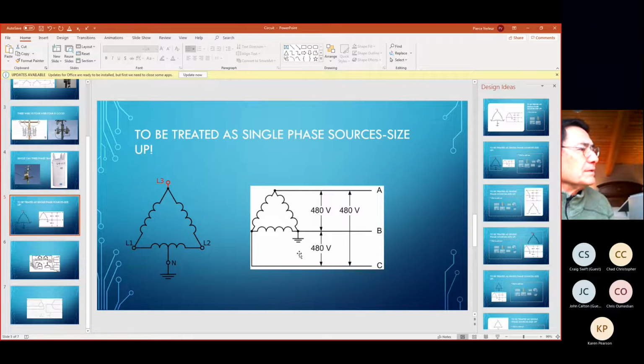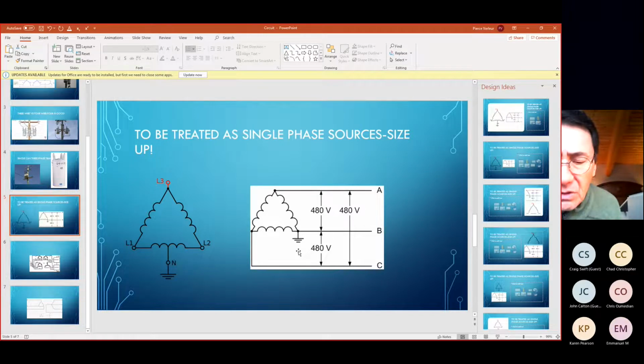The second one is corner grounded delta. In other words, another method of picking up the ground. These were prevalent in the times when most of the usage in the agricultural area was single phase and then some 3-phase loading. And honestly, when you put motors on this, they're seeing their imbalance, and the motors basically took it and had reduced life. You put a drive in there, and as I said earlier, the motor is now relieved of the imbalance, but the drive must take it. And in the case of the drive is a little bit less tolerant. It'll either trip out or pretty much blow up quickly, again, because of those capacitor heating issues.